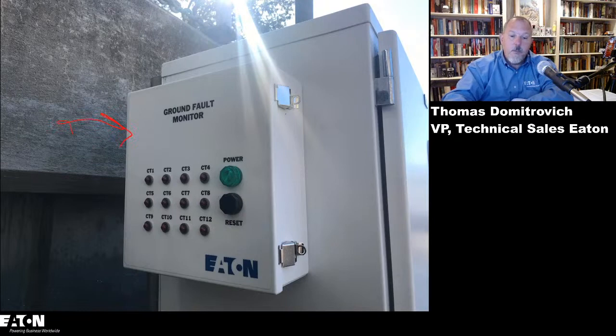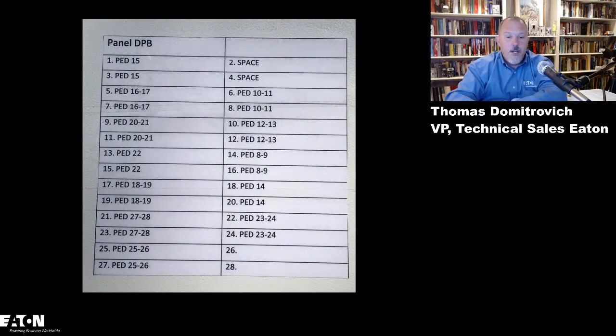And this device here, a ground fault monitor, these lights provide an indication. If I'm not mistaken, I believe there's an audible alarm. I don't want you to hold me to that one. I believe there is an audible alarm, though. I'd have to talk to Cliff to find out if that's 100% accurate. But that gives you an indication of which pedestal has ground fault leakage current exceeding, I believe this is 30 milliamps. There's a lookup table. So you have pedestal 15, all of the different pedestals.